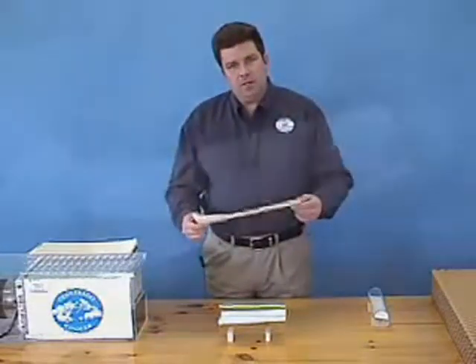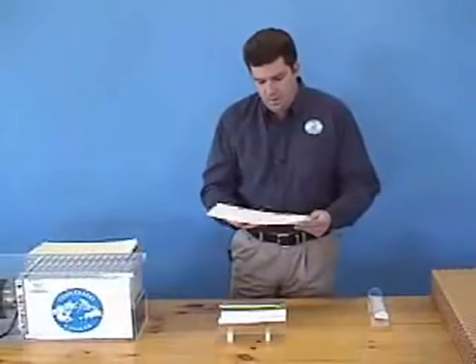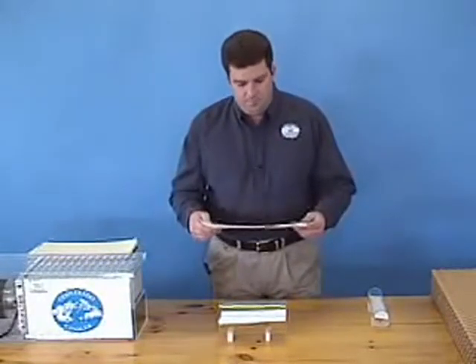This is a plastic-coated piece of paper. It is paper on one side, coated with a thin layer of plastic on the other. If you wet one side of this paper with water and blow air past it, the water evaporates from the paper and cools the plastic. In this process, you are exchanging mass in the form of water to vapor in the air. The plastic is the heat exchanger, and it in turn will cool and pull heat away from the air on the other side. This is similar to how your body, skin, and perspiration work together to cool your body. Indirect evaporative cooling is called sensible cooling, and heat energy is removed from the product airstream.